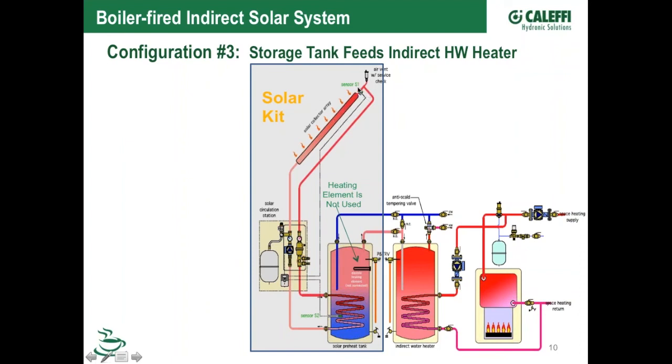Well, this sensor up here is going to keep an eye on that temperature, and it's going to say, you know what, I think the factory default is 275 degrees. It's adjustable. Say, you know what, I got a lot of heat in here. I'm worried about the glycol being exposed to the high temperature. I'm just going to pulse that pump and turn that pump on for a period of time, and I'm going to just run that for 30 seconds, I think is the default on it. And I'm just going to flush all that glycol that's inside that collector out, and I'm going to send it down to the tank, even though the tank doesn't want it or says, you know, I've got enough. So it's going to do that until you get to a high limit on this tank temperature. Obviously, we don't want to take it over where the relief valve is going to pop. So it'll just keep pulsing a little bit of temperature in that, a little bit of temperature. And so what it's going to do, it's going to overshoot the temperature that you've got this tank set for.